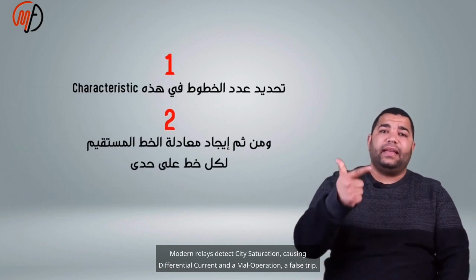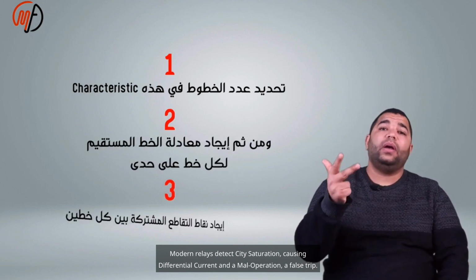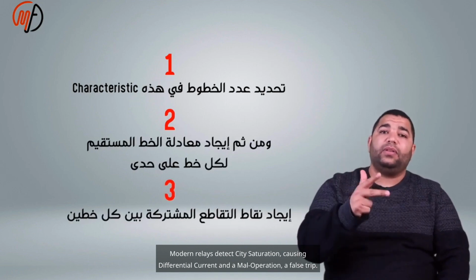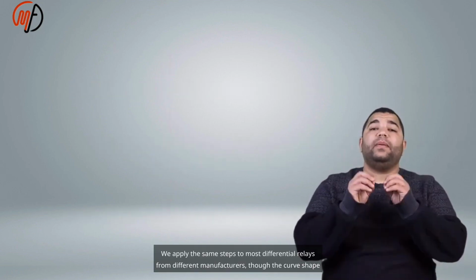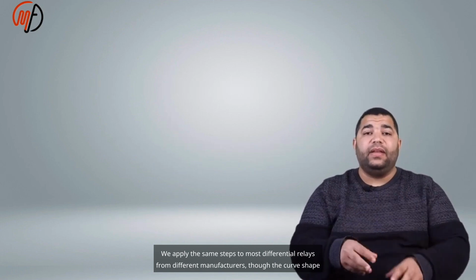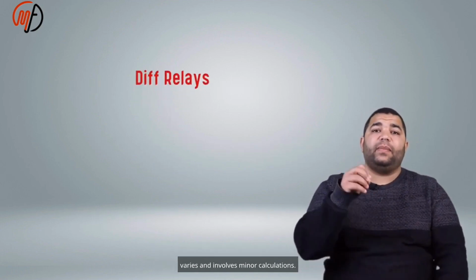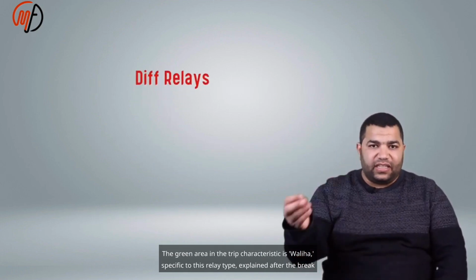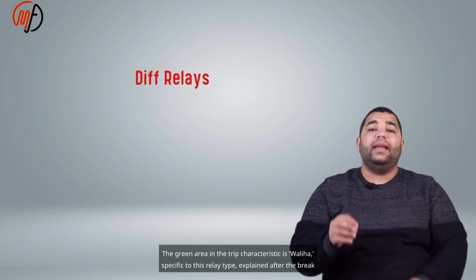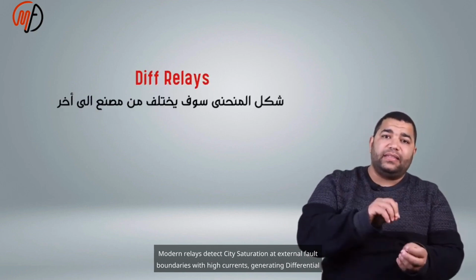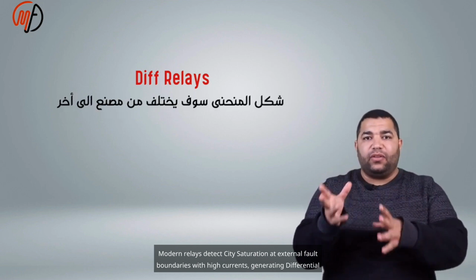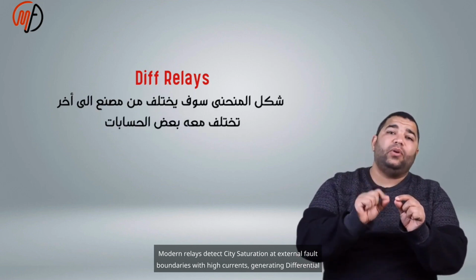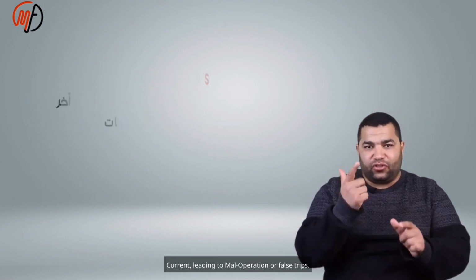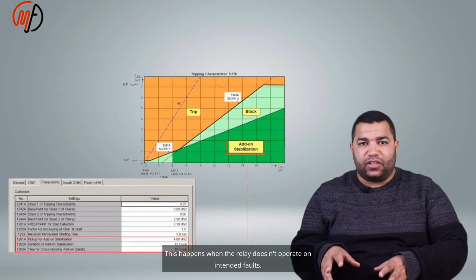Modern relays detect CT saturation, which causes differential current and a maloperation, a false trip. We apply the same steps to most differential relays from different manufacturers, though the curve shape varies and involves minor calculations. Modern relays detect CT saturation at external fault boundaries with high currents, generating differential current, leading to maloperation or false trips.